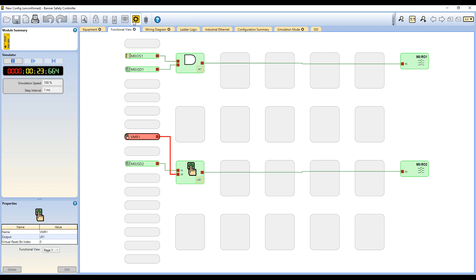Now I can simulate it. I hid some stuff for this demo, but you click the simulate button and you'll see I need both my light curtain to be okay and the doors closed for that first channel to turn on - that works how I expected, I didn't pick an OR gate by accident, which can happen. The E-stop, once armed, won't turn the output on until it receives a virtual reset, or a hardwire reset however you do it. So it works the way you planned, which is fantastic.